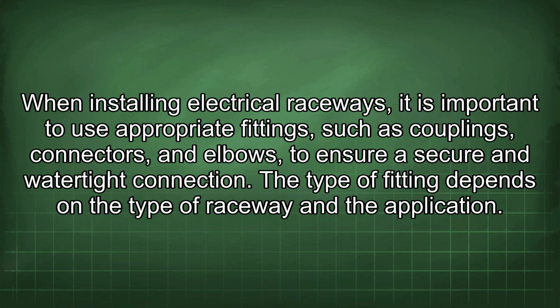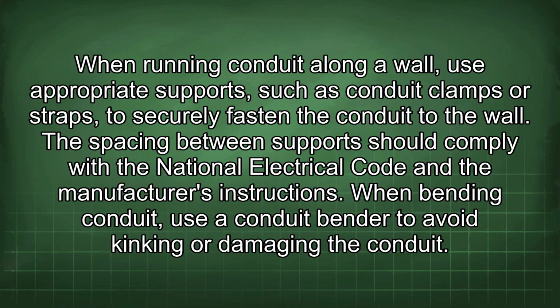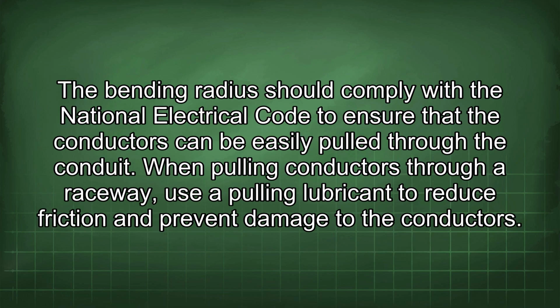When installing electrical raceways, it is important to use appropriate fittings such as couplings, connectors, and elbows to ensure a secure and watertight connection. The type of fitting depends on the type of raceway and the application. When running conduit along a wall, use appropriate supports such as conduit clamps or straps to securely fasten the conduit to the wall. The spacing between supports should comply with the National Electrical Code and the manufacturer's instructions. When bending conduit, use a conduit bender to avoid kinking or damaging the conduit. The bending radius should comply with the National Electrical Code to ensure that the conductors can be easily pulled through the conduit.